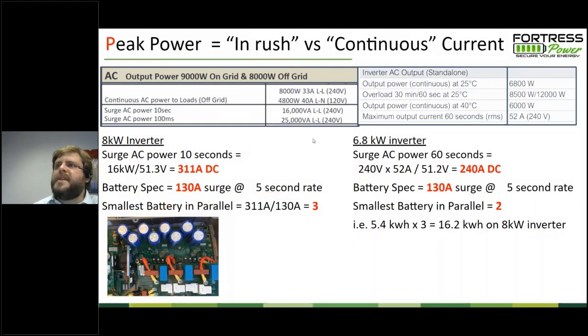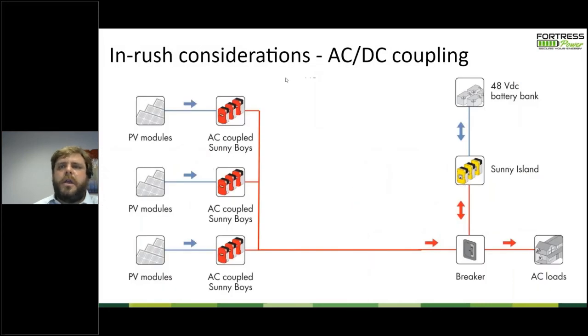And so really where we see that error occur is when you have multiple inverters, in this case with AC coupling. You could also have it on the DC side with DC coupling, where you have multiple charge controllers. If you turn them all on at the exact same time, with just a second in between, each inverter, flip, flip, flip, flip, versus flip, wait a few seconds, flip, wait a few seconds, flip, wait a few seconds. One will have the inrush currents overlap, the other will have them staggered out.